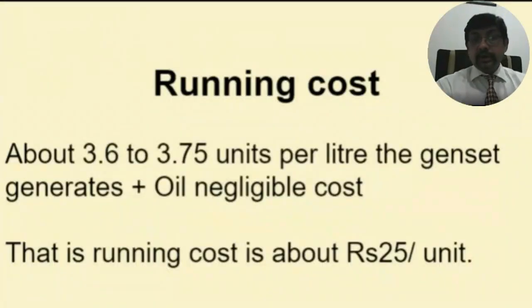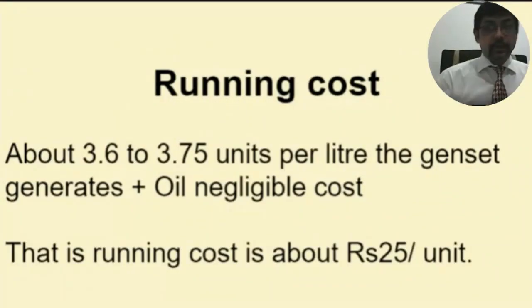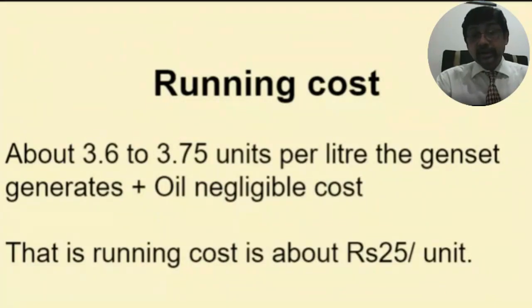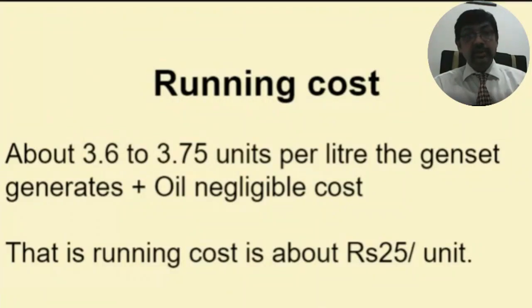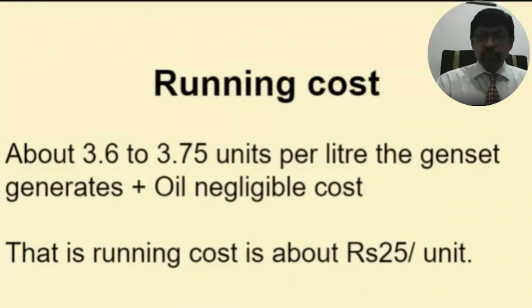Next. Now, coming on to the running cost of the generators. Of course, with the diesel and petrol prices going sky high, the cost of diesel generators is also going high. Now, a normal generator between 30 kVA to, say, 250 kVA in the medium size of industry, generates about 3.6 units to 3.75 units per liter of diesel. And of course, a small amount of oil is also required there.